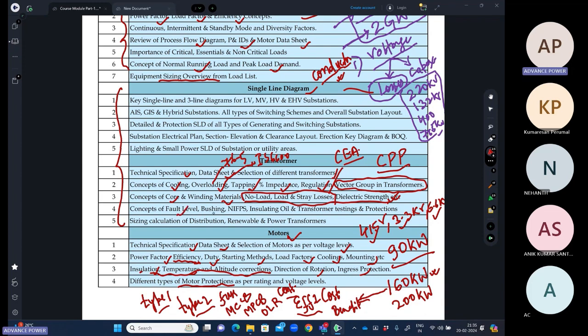We'll discuss the concept of fault level, bushings, the nitrogen injection fire protection system, insulating oil parameters, which is affecting based on the temperature, different transformer testing, in which the short circuit of the transformer is always being discussed during any project, that do we require a transformer which is having a short circuit tested, because it's a special type of test and it's a destructive test. So we'll discuss about the similarity criteria also as per IEC 76 part 5 annexure B, and we'll discuss the different protection in the transformer, and from here it will be comparable to different transformer which is being used in the different industries.